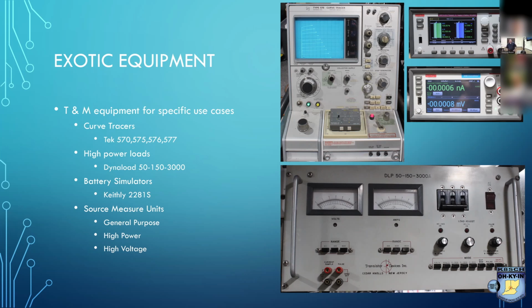Source measuring unit is one of the other odd ones. It's a very, very precise, perfect current source within its power band. So if you ask it to put out a milliamp, it'll drive to 200 volts to try to put out that milliamp. So it can measure extremely high resistances very accurately. That's the one device that gets me into the tera ohm range, it will literally measure the resistance of the plastic banana jacks when you put it into the outputs.